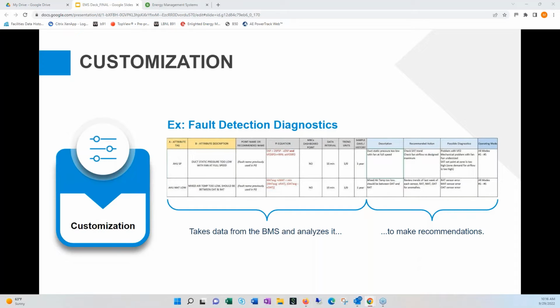It's kind of small on screen, so don't worry about reading it exactly. Ultimately, the intent behind a fault detection diagnostic is to tell if your system is performing properly or efficiently. It's very different from an alarm from your building automation system, which might just say a piece of equipment is broken or not working. This is trying to be proactive and preventative, confirming that your system is running efficiently.